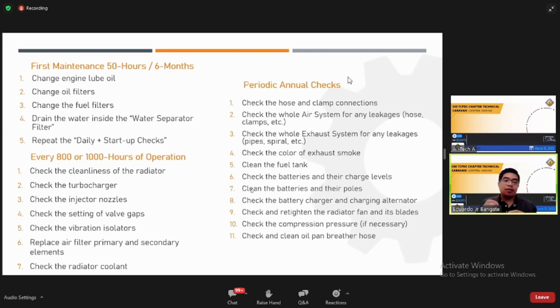Because, especially when your generator is new, everybody knows that a new engine is a bit tight. So there are possibilities that some metallic parts came off from its structures, its components, and mixed with the oil. Sometimes because the generator is new, we can't easily see these, they are microns. So it is better to follow the requirement or recommendation of the manufacturer to prevent damage to the generator and for us to get the maximum efficiency of our generators.